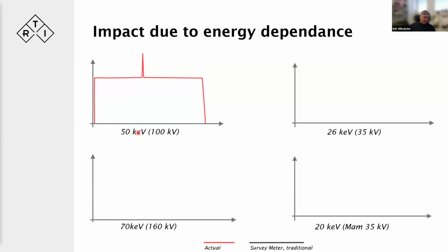So if we're at 50 keV, at that point we'll see it traces the reading pretty well. It will rise slower because, of course, it has a longer response time to reach that value. And if there are some bumps in the road or some peaks, it will also react, but slowly to that phenomenon. But it will give us a max reading which is true, which is the same as the actual tube output.